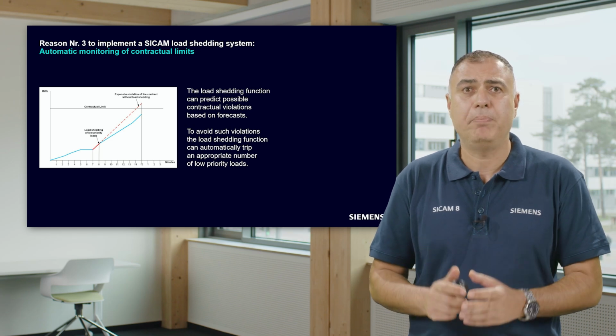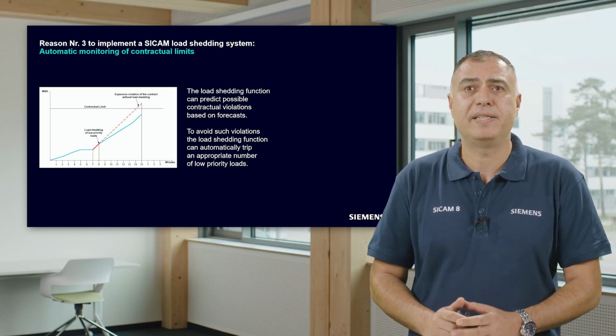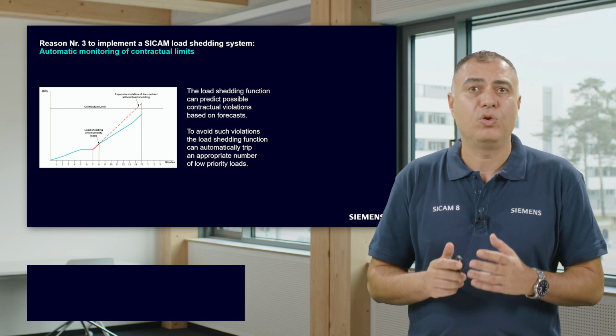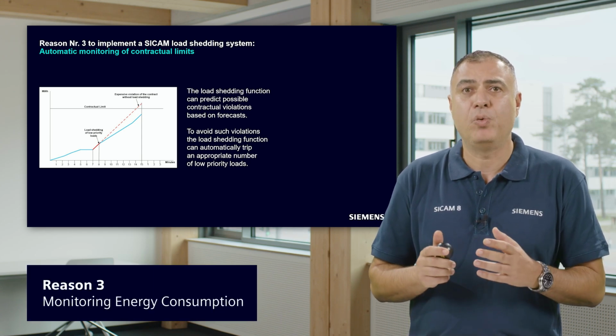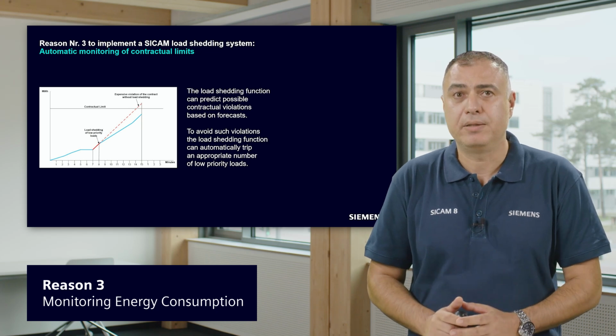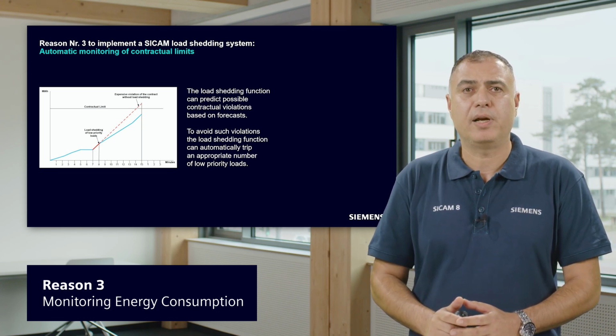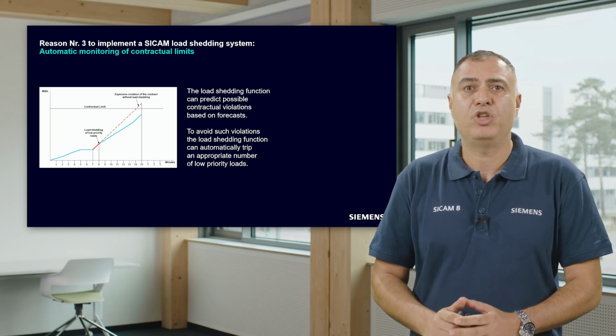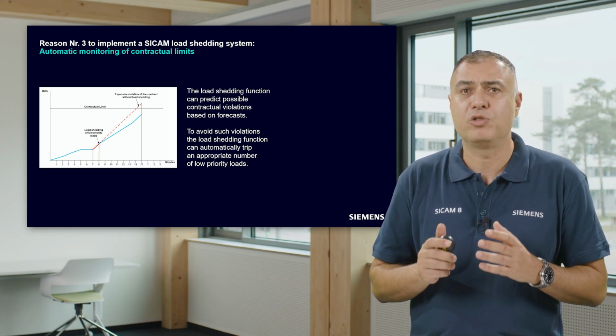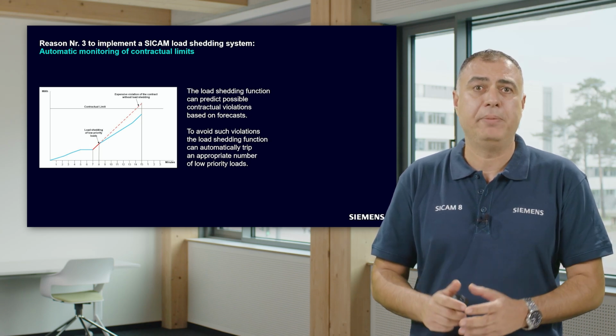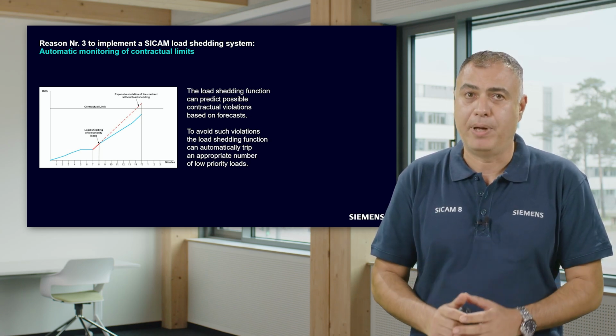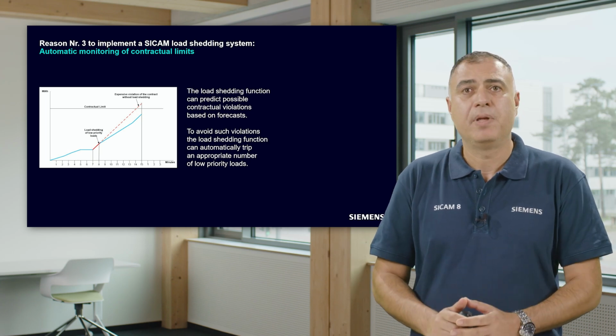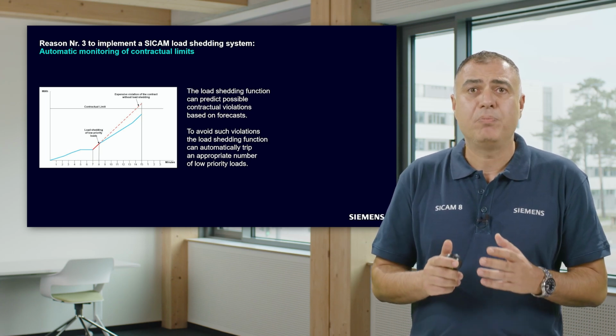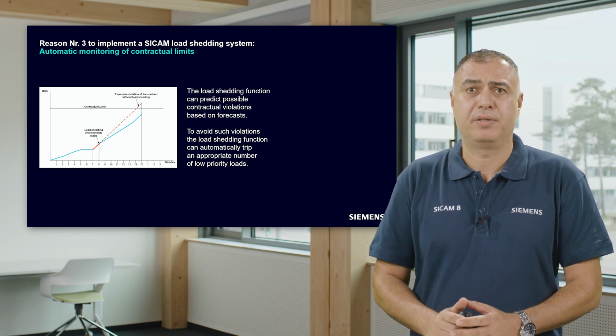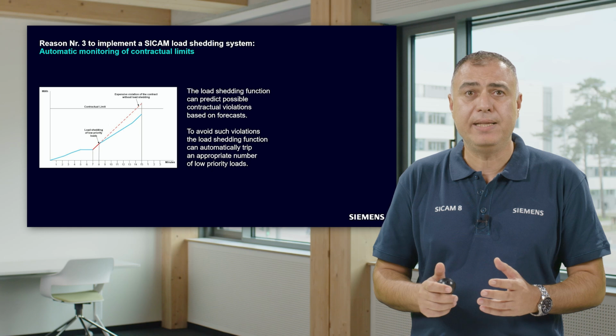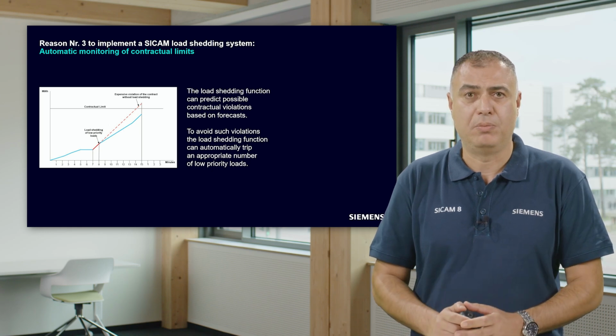In the shown example, the start of the energy monitoring was selected for minute 7. The load shedding system automatically extrapolates the energy consumption of 1 minute. If a violation of the contract is predicted, the load shedding system sheds the necessary number of low priority consumers. This procedure will be repeated until the end of the monitoring period. This function makes it easy to prevent possible effects of the contractual violations. Other algorithms for predicting energy exceedance are also possible.